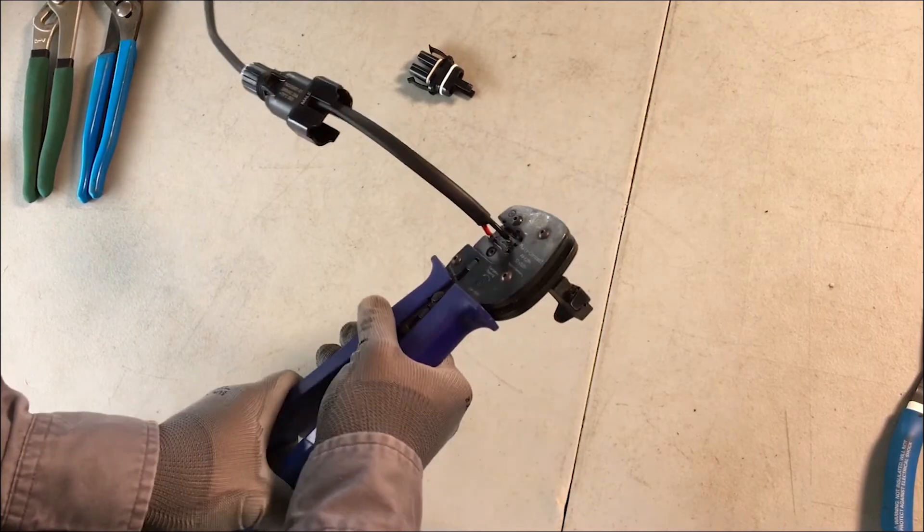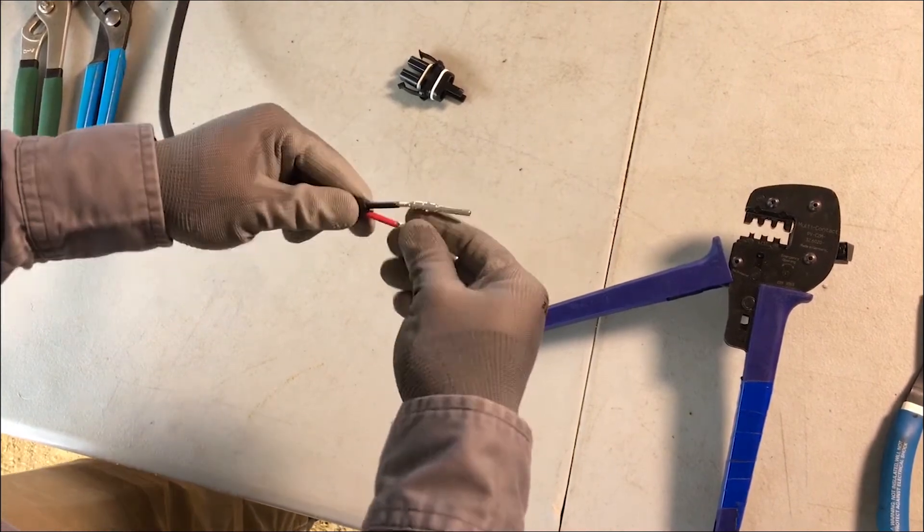Only use the terminals provided with the connector package. Release the crimp tool and tug the terminal to test the integrity of the crimp. Repeat these same steps for the black conductor.